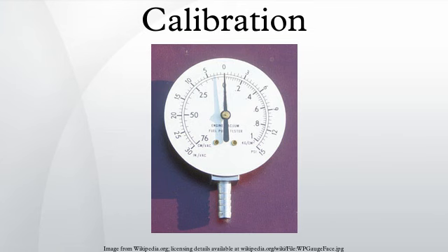The small horizontal unbroken paper seals connecting each instrument to the rack prove that the instrument has not been removed since it was last calibrated. These seals are also used to prevent undetected access to the adjustments of the instrument. There also are labels showing the date of the last calibration and when the calibration interval dictates the next one is needed. Some organizations also assign unique identification to each instrument to standardize the record keeping and keep track of accessories that are integral to a specific calibration condition.